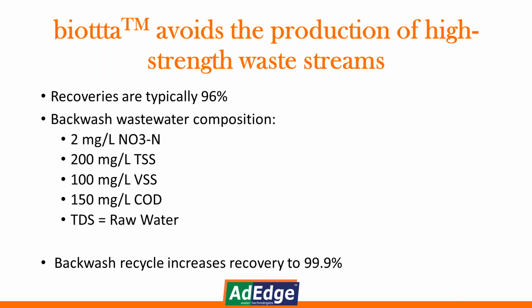There are several methods by which those could be managed, including filter presses, sludge drying beds, even just a sludge holding tank and having that hauled at some point, or actually discharged direct to a sanitary sewer. And as you can see, the TDS of the water is the same as the raw water, you have a little COD, TSS, and nitrate, but this is typically a very acceptable waste stream for a wastewater plant.